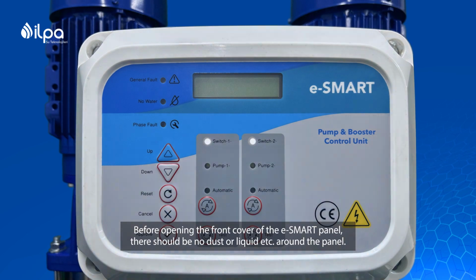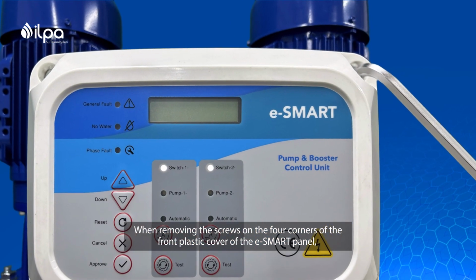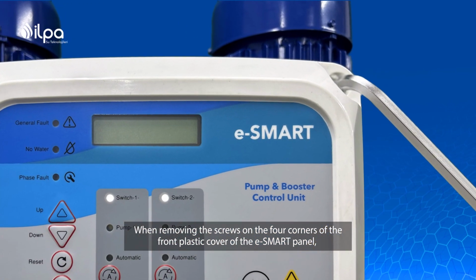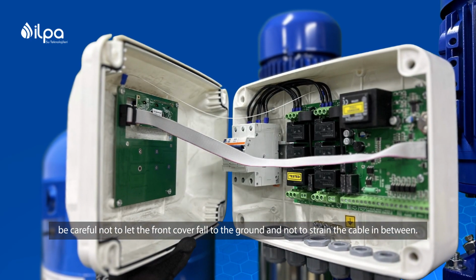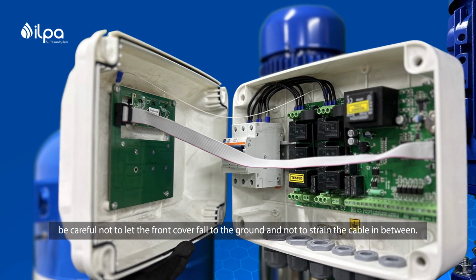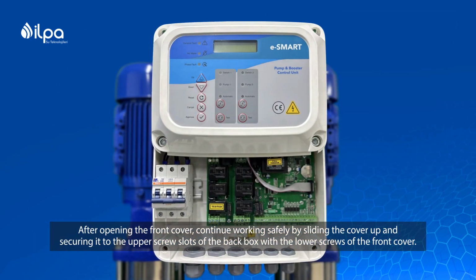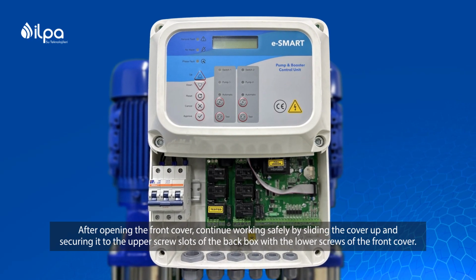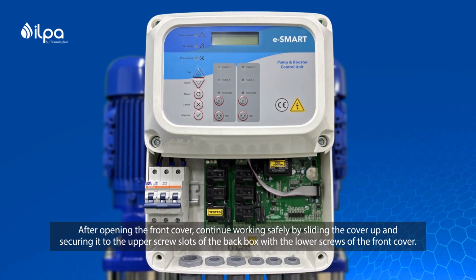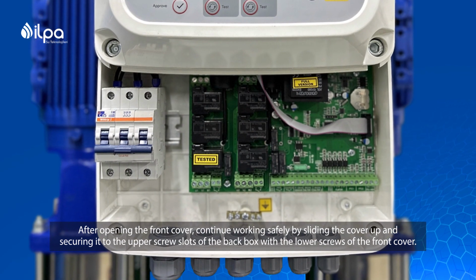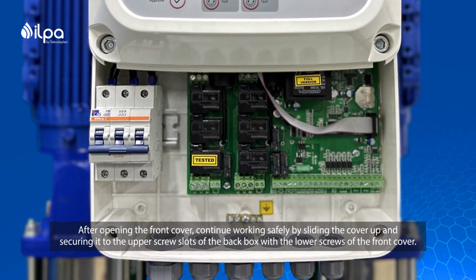etc. around the panel. When removing the screws on the four corners of the front plastic cover of the eSmart panel, be careful not to let the front cover fall to the ground and not to strain the cable in between. After opening the front cover, continue working safely by sliding the cover up and securing it to the upper screw slots of the back box with the lower screws of the front cover.